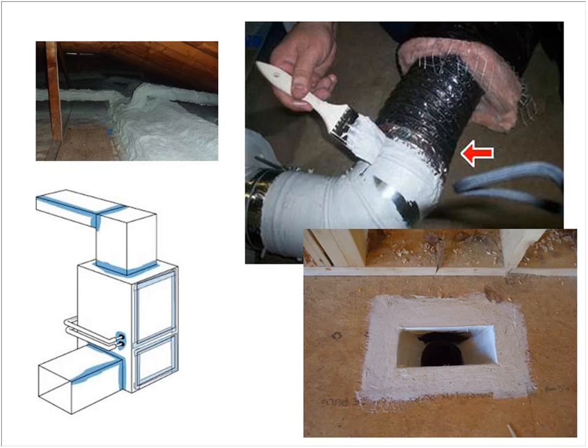So if the ducts were laid down so that you could cover them after they've been sealed like that, then that would be an acceptable method of avoiding testing, because it's considered a bulkhead. Otherwise, you can see how they're painting a mastic on that connection in the attic before they stretch the insulation over the top and band that into place. It's very, very important that everything else be sealed with a mastic, because it doesn't take much leakage to fail a test.